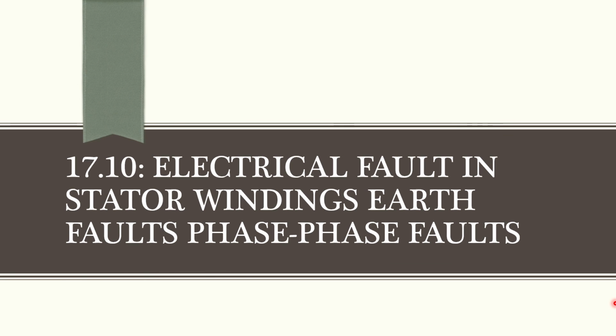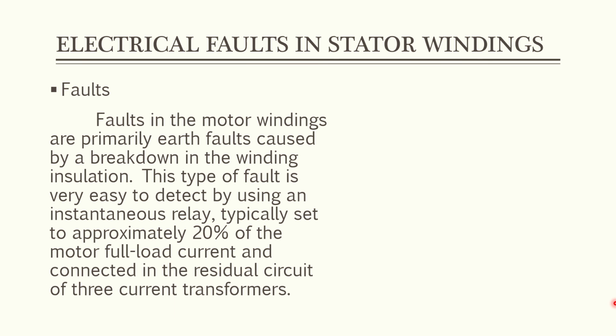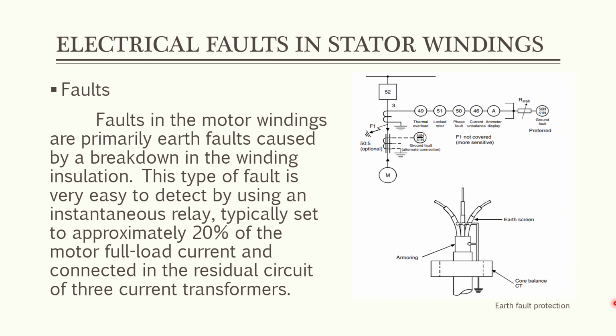Electrical fault in stator windings, earth faults, phase-to-phase faults. First, what are faults? Faults in the motor windings are primarily earth faults caused by a breakdown in the winding insulation. This type of fault is very easy to detect by using an instantaneous relay, typically set to approximately 20% of the motor full load current and connected in the residual circuit of 3 current transformers.